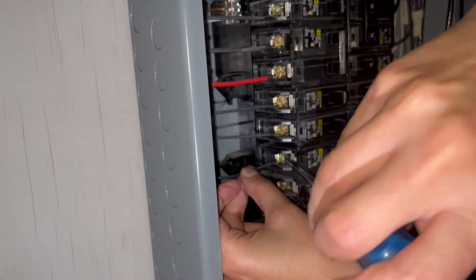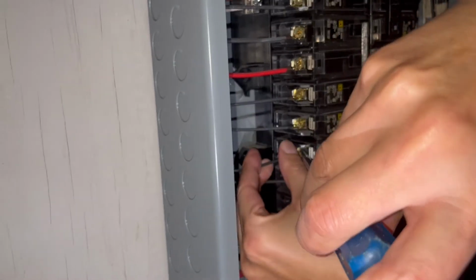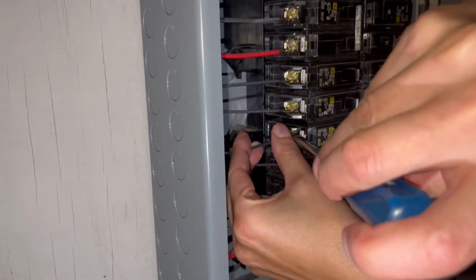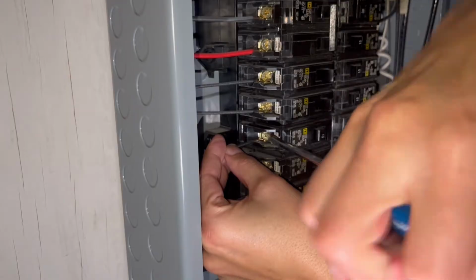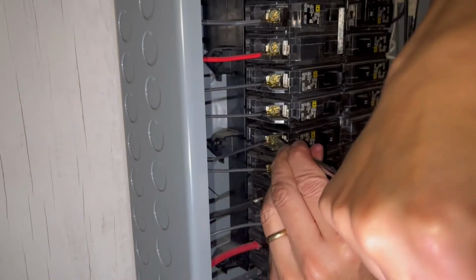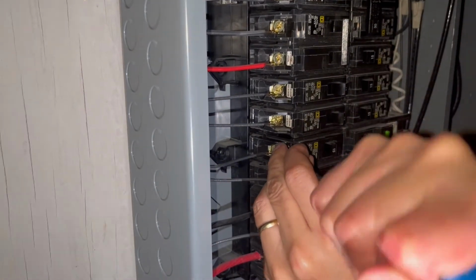Now on the side of that circuit breaker, it actually had all your data. It had the amperage size. It had the wire sizes allowed. It had the heat rating. It had the torque rating on how tight to make this screw setting. All right, we're all set.